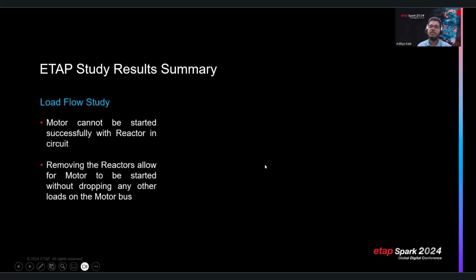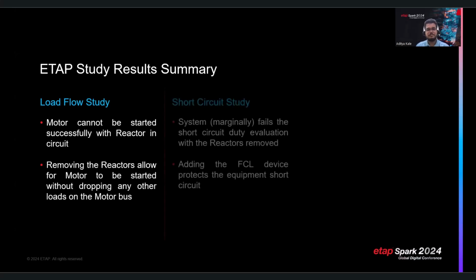Back to the presentation, let's summarize the ETAP study findings. We looked at the load flow study where we saw the motor cannot be successfully started with the reactors in circuit. This was primarily due to the low initial motor bus voltage. Removing the reactor does boost the initial voltage up to a comfortable level where the motor can be started without dropping off any other loads.